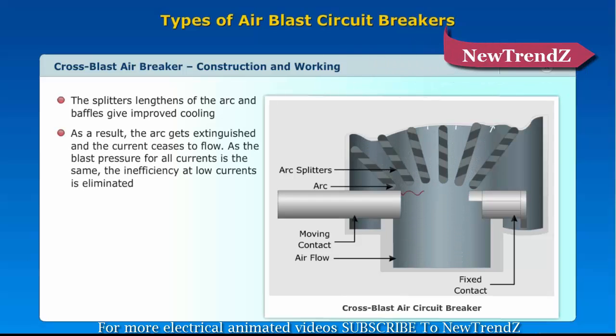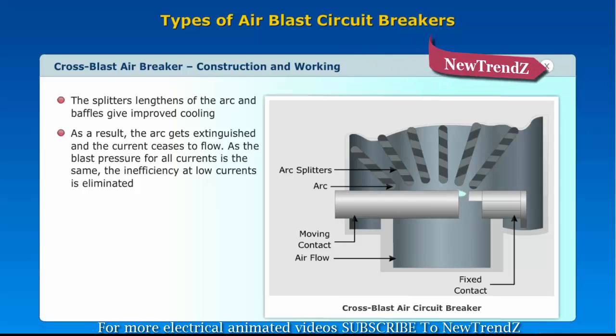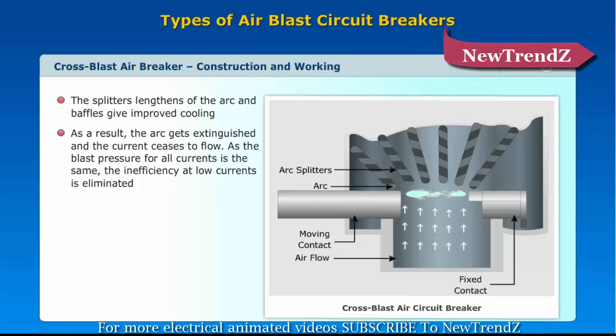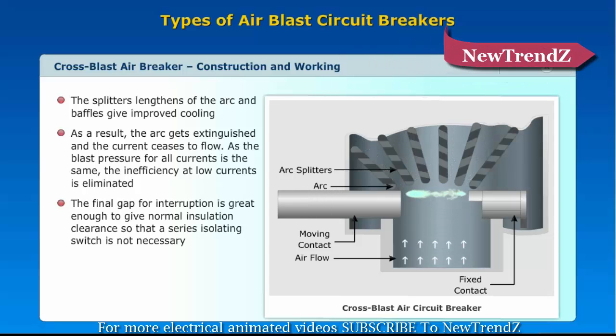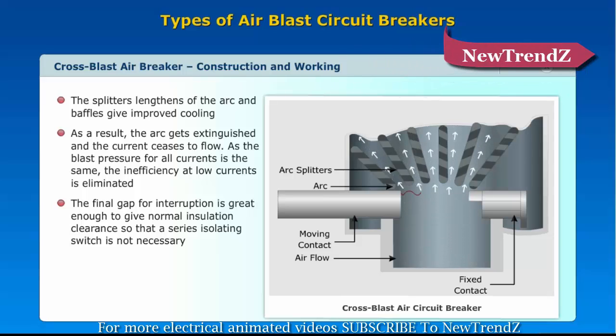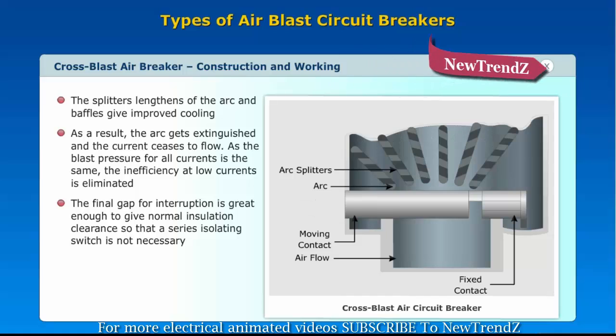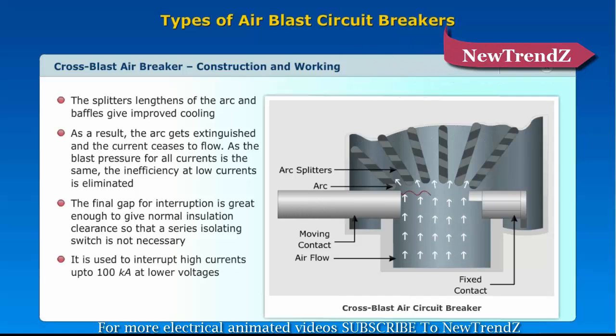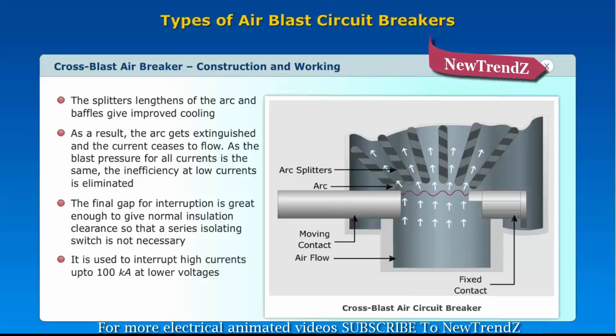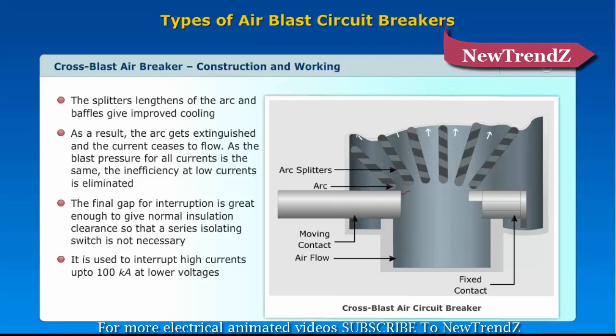The splitters lengthen the arc and the baffles give improved cooling. As a result, the arc gets extinguished and the current ceases to flow. Since the blast pressure for all currents is the same, inefficiency at low currents is eliminated. The final gap for interruption is large enough to provide normal insulation clearance, so a series isolating switch is not necessary. It is used to interrupt high currents up to 100 kA at lower voltages.